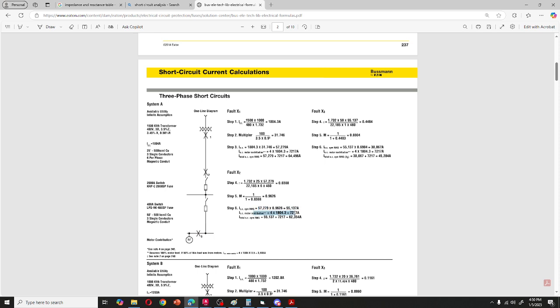Then for the motor contribution, same process again. Total SC for RMS is 55,137 plus the motor contribution, which is 62,354 amperes.